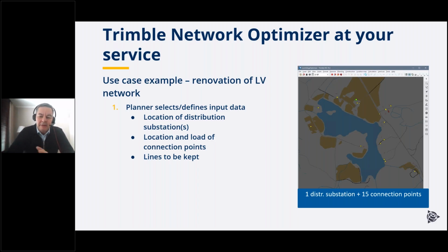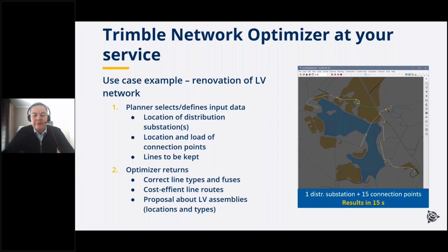After selecting those few components, in this case one distribution substation and 15 connection points, the planner presses the magic 'optimize' button, and the optimizer returns correct line types, makes protection calculations, defines needed fuses, finds the most cost-efficient line routes between the nodes, and proposes locations for low voltage assemblies and distribution cabinets.